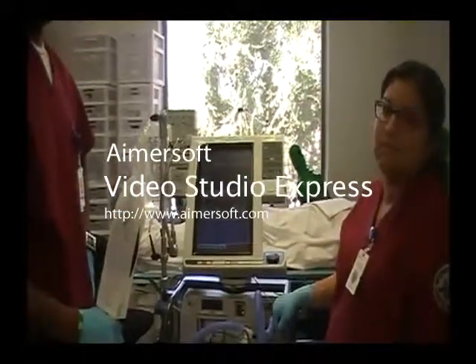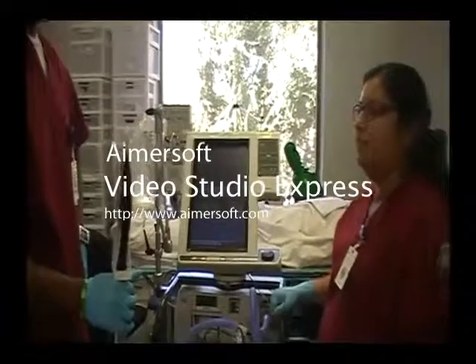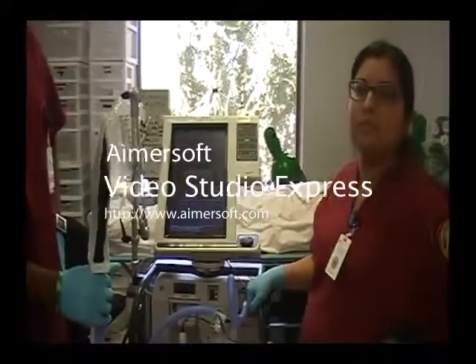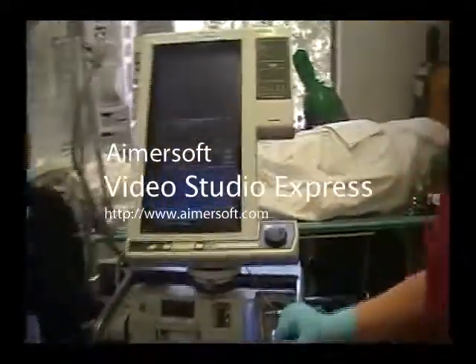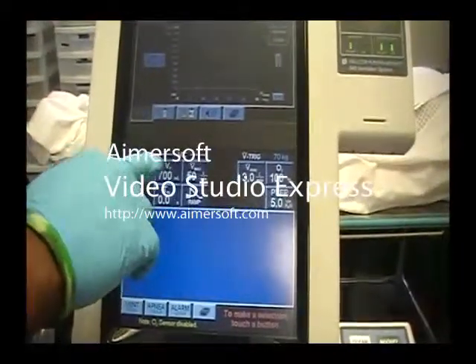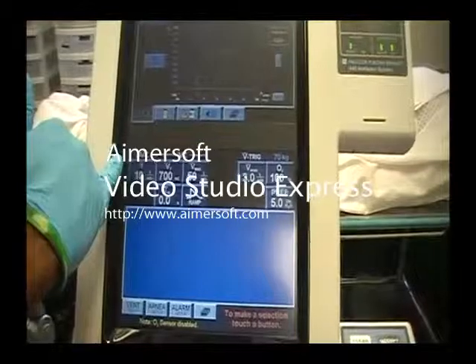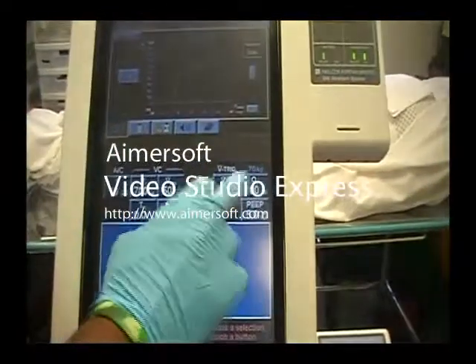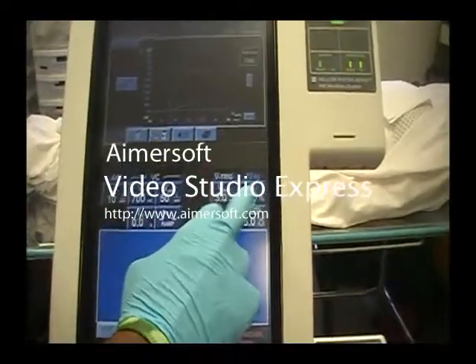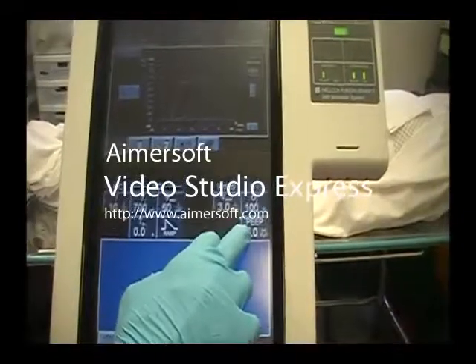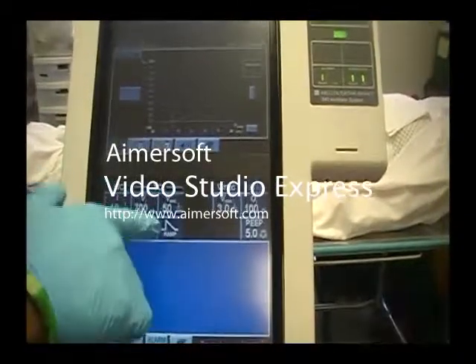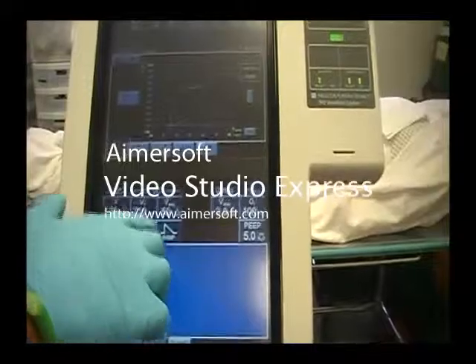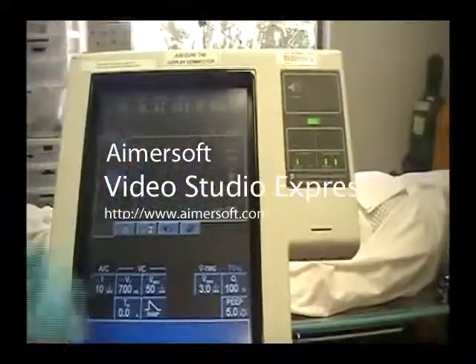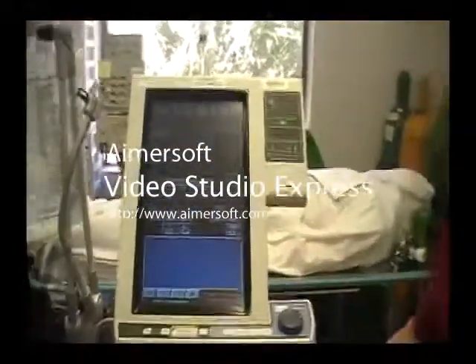Okay, so after the vent has passed all of the proper testing, we're going to adjust the ventilator to the ordered settings. Settings we chose for the 70 kilogram patient: we have a 700 tidal volume, a respiratory rate of 10, an FiO2 of 100%, PEEP of 5, flow at 50, and a ramp waveform. And that's it. Those are the patient settings.